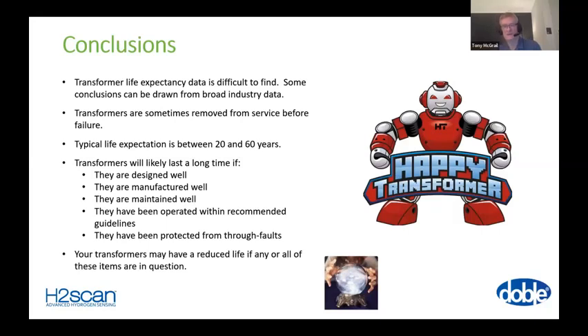That should be what I would expect to be a minimum. And we then have to vary that depending on how we drove the transformer, what faults it's seen, what maintenance it's seen, what overheating it's had, whether it's been dried out, et cetera, et cetera. And that has to be added in. So to me, on day one, for a well-specified, well-built transformer, I want at least 60 years. And it's going to reduce from that depending on what I've done with it.